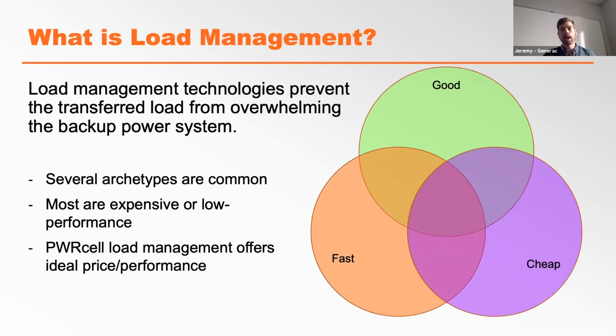So now we know why load management is important. Let's talk about what it is. Broadly speaking, load management technologies prevent circuits from drawing more than the backup power system can serve. Some loads will be prevented from running simultaneously -- for example, the AC unit can't run at the same time as the hot water heater -- but they'll be able to run independently of each other.